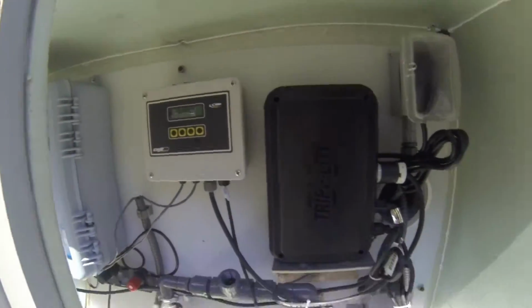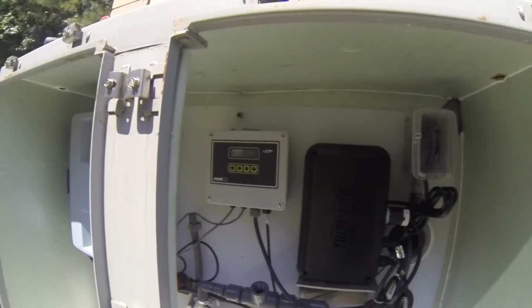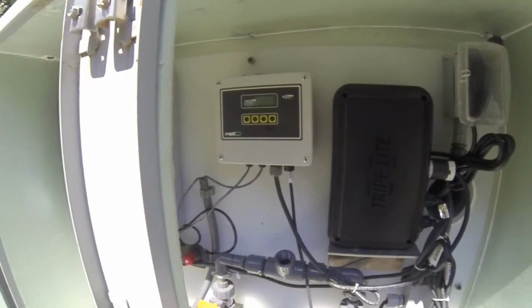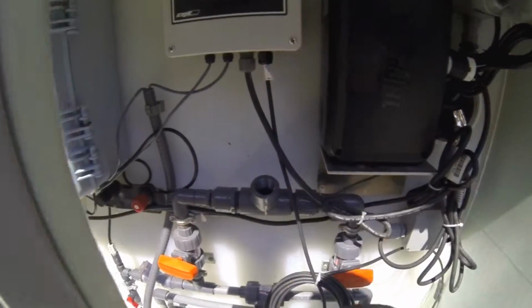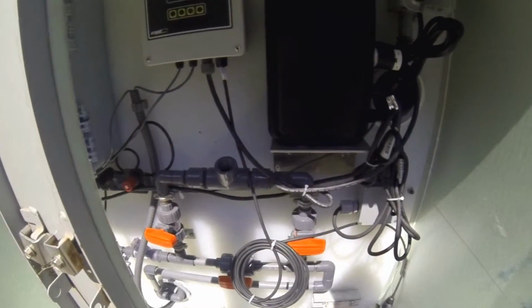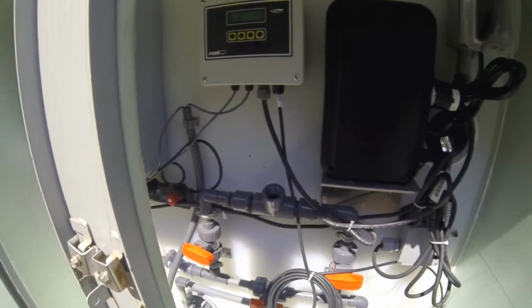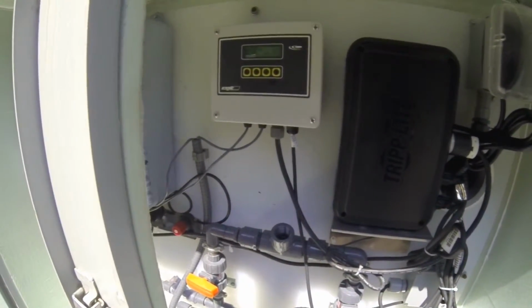All I'm going to do is put it back into 4 solution, make sure that we're reading 4. Put it back into 7 solution, make sure that we're reading 7. Then I'm going to Teflon tape the probe, stick it back into its appropriate hole, open up the valves so it has a continuous flow of water over it, and that should conclude changing out a pH probe.